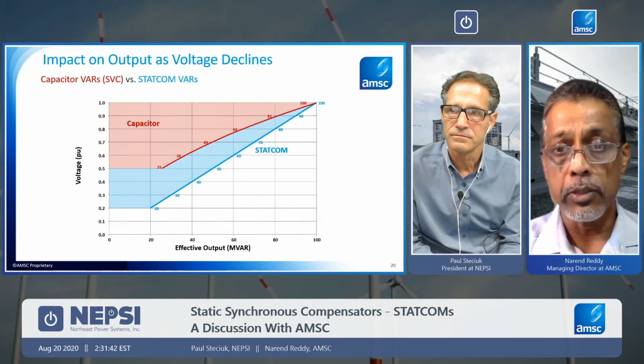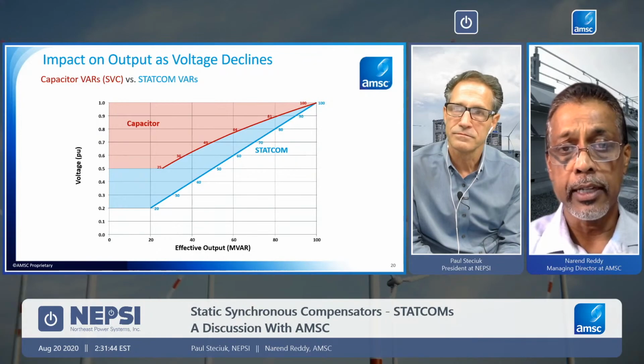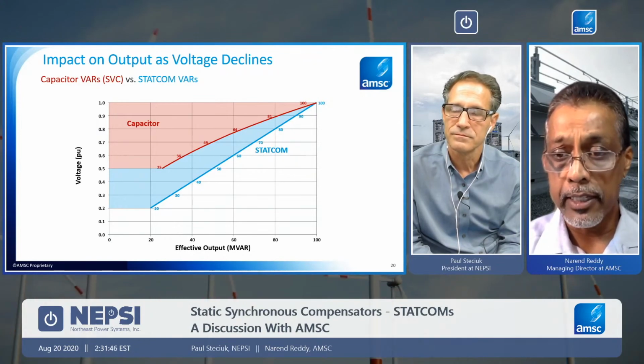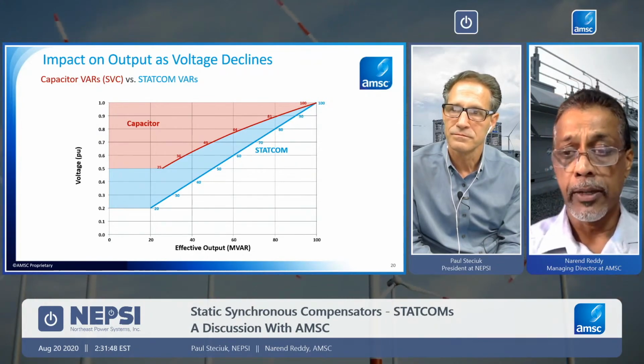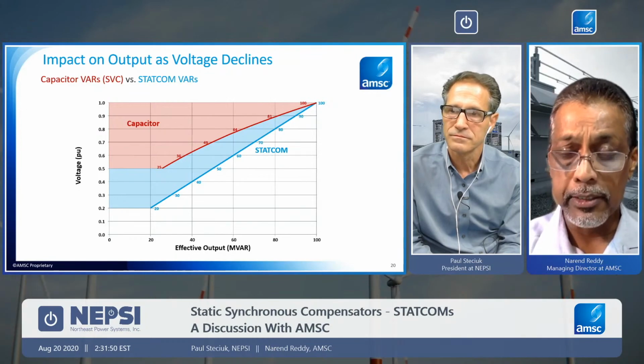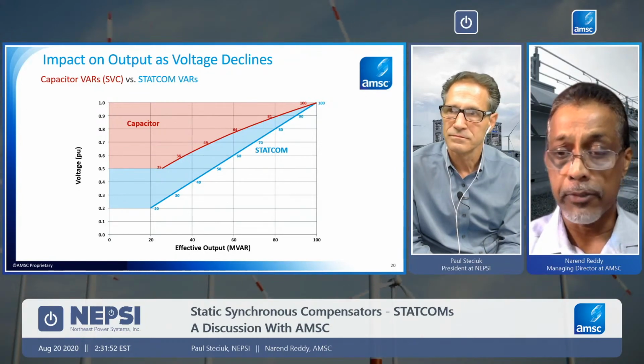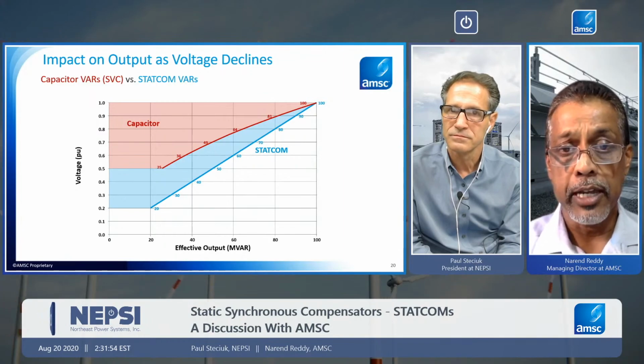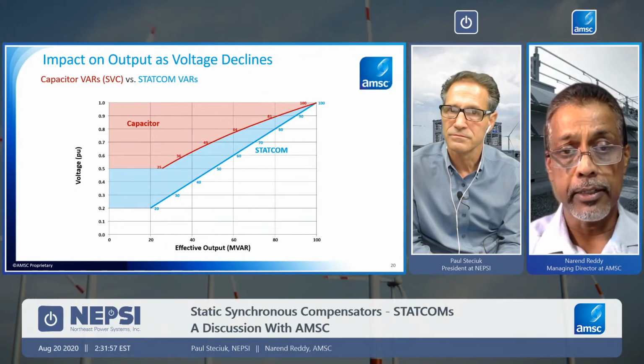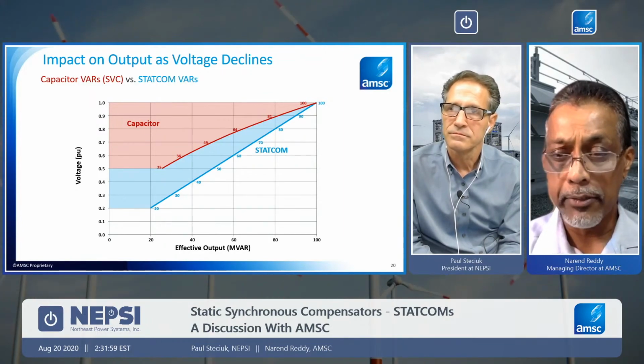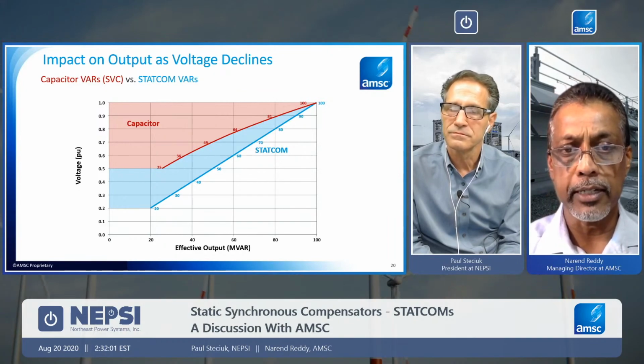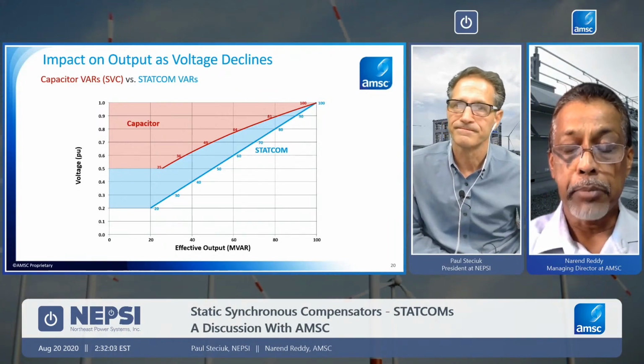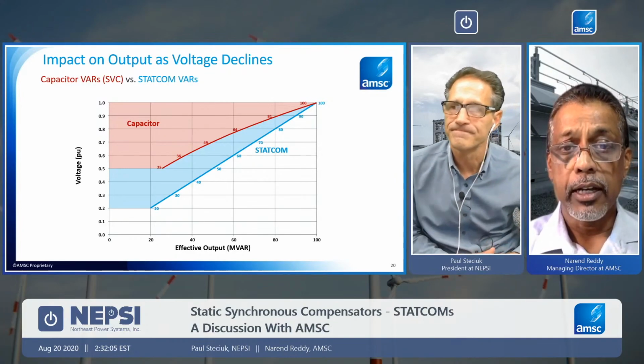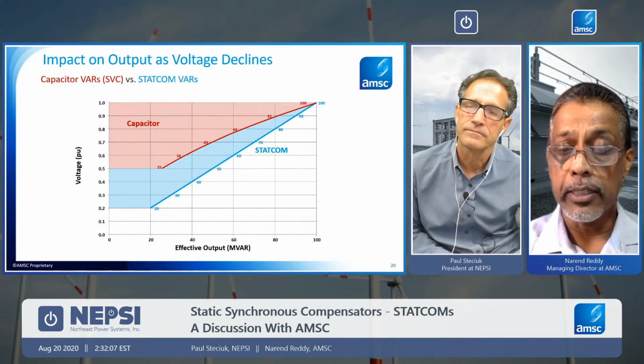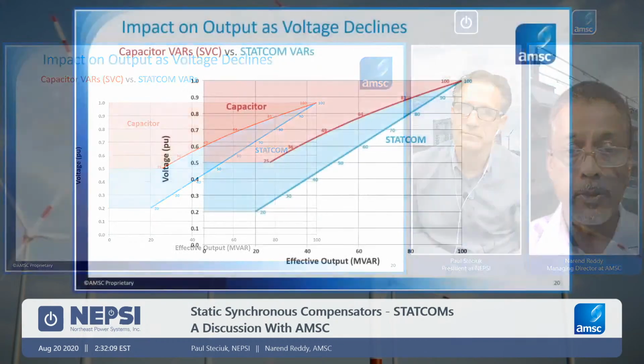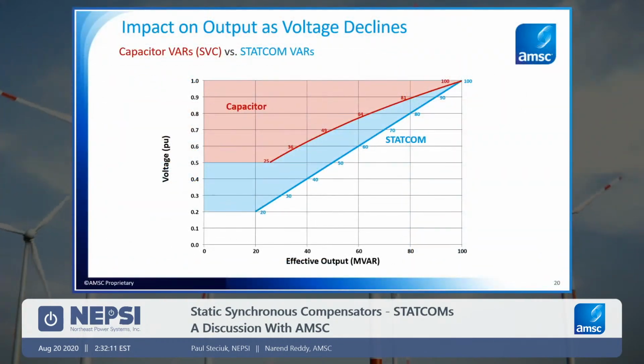Another point to note here is that the red graph really cuts off at about 50%, which is where SVCs typically would cut off. At 50% voltage or less, thyristors are blocked off and won't be operated. Typically, that's 70% or greater, but we've seen that come down in some cases. But for STATCOMs in general, you'll note that my graph is showing that we can go down to 0.2 per unit, or in some cases even lower than that.